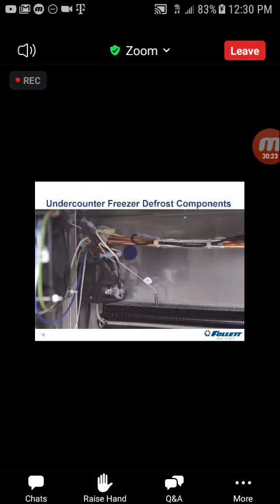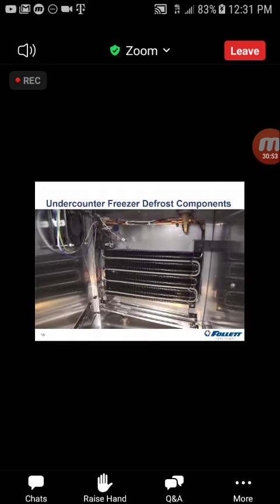Components inside include the defrost termination probe, which is labeled the P2 probe on the control board. The purpose of this probe is to terminate the defrost cycle when the evaporator temperature reaches 5 degrees Celsius, which is the equivalent of 41 degrees Fahrenheit. Slightly above that, there is a safety switch, commonly called a Klixon, which will take the heater offline if the evaporator gets too hot. This is a safety feature, and that switch should be closed all the time.